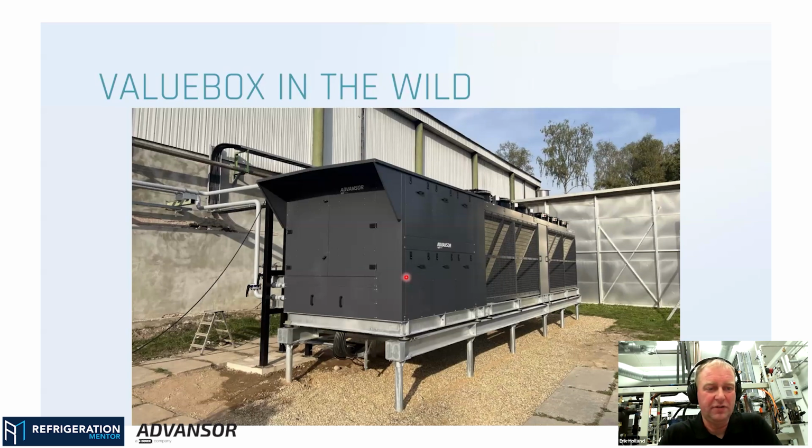But then we found as soon as you have enough liquid to run the unit, it's easier to charge from your liquid line. So you close your separation valve between your liquid receiver and your liquid line, then connect somewhere after that with your CO2 hose, and charge with liquid that way, and just let the compressors do the work for you. That worked quite well in the systems here.